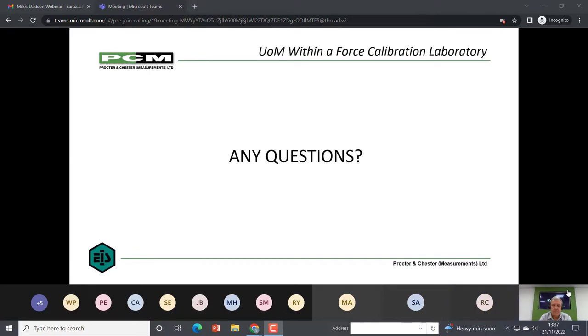Okay, we have another one coming in. Another one from Stuart Edmonds, I should have said: how do you decide temperature uncertainty for a strain gauge load cell? All the temperature coefficients of all the instrumentation that we've got to achieve the measurement come with their own specifications from the manufacturers, of what drift it will be across. Normally it's given as a 10 degree Kelvin range, but because we specify that ours are carried out within 1 degree, that's what we adopt. If you're talking about the load cell itself, that is somewhat down to the manufacturer of the load cell or the device under test. Thank you. He says thanks.